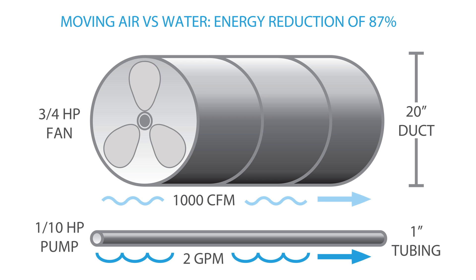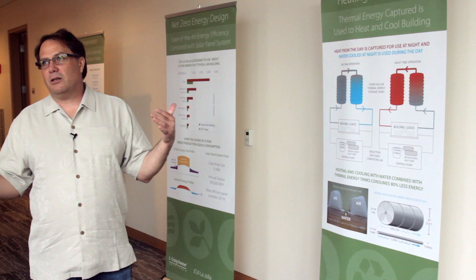That amount of air would require a 20-inch duct with a three-quarter horsepower fan. We can move the same amount of energy through a one-inch tube with only one-tenth horsepower, so it's significantly less energy.